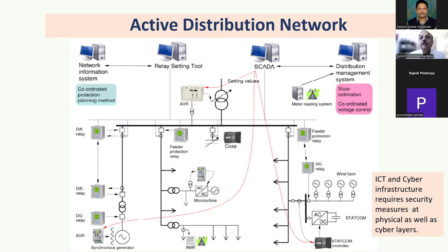So what will change? Distribution will also become active with ICT infrastructure and cyber infrastructure in place. They need sensors to sense various data, not only from renewables but also from controllers downstream. They need a distribution management system to operate through SCADA, and very intelligent relay setting and coordination protection tools. This is how it's being transformed into an active distribution network.